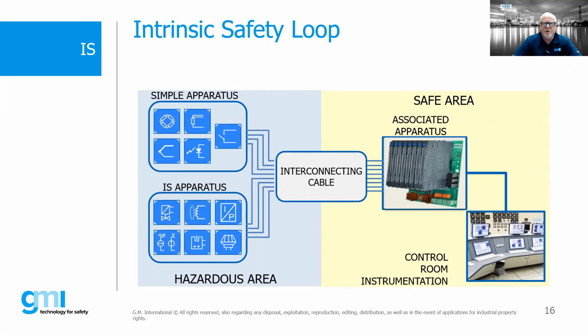So part of intrinsic safety is what is called our intrinsic safety loop. This is a little more detailed information than what we just showed previously. So again, simple apparatus or IS apparatus with our interconnecting cable, our associated apparatus, our control room instrumentation. Notice on the right-hand side, we have our safe area or non-hazardous area. And then of course, the devices themselves are located within a hazardous location. That does not mean that our associated apparatus cannot be installed in a hazardous location, but we have to take that into account. In some cases, it is actually a requirement, because the distance of our interconnecting cable might be a factor where there's more storage of energy, so we have to locate those associated apparatuses closer to the simple or IS apparatus in the field, which we can talk about a little bit later. But this is our intrinsic safety loop, and we have to have an intrinsic safety loop calculation for every IS installation that we do.